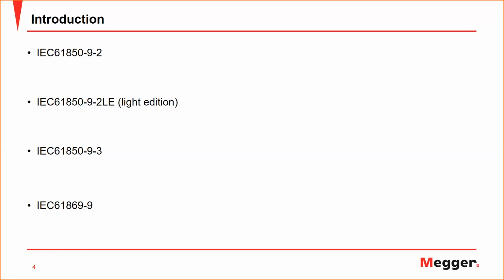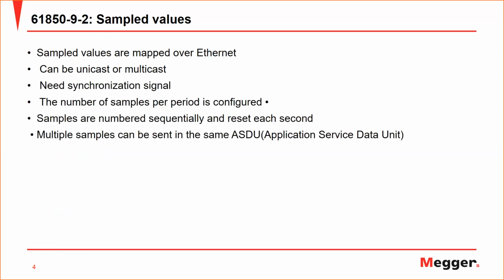So if we want to go into more detail in -9-2, it is, as I mentioned earlier, sampled value mapped over Ethernet. But this value, once we connect it to an Ethernet switch, will be mainly, I would say, published or multicast. But because of time delays and different network paths for different merging units, we will require synchronization or time synchronization. For these sampled values, from the name sampled, you have to define how many samples happen per period or per cycle. So the subscriber to these published messages over Ethernet understands and is able to analyze the value correctly, similar to what happened in the analog environment.